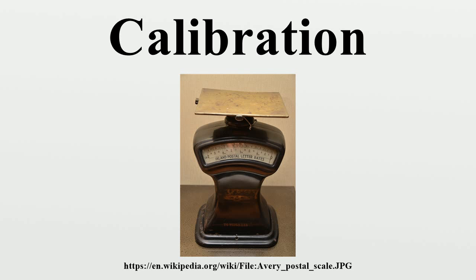This is a simplified example, and it is important that whatever thinking guided this process in an actual calibration be recorded and accessible. Informality contributes to tolerance stacks and other difficult-to-diagnose post-calibration problems. Ideally the calibration value of 100 units would be the best point in the gauge's range to perform a single-point calibration. Multiple point calibrations are also used. A zero unit state — the absence of the phenomenon being measured — may also be a calibration point, or zero may be resettable by the user. There may be specific connection techniques between the standard and the device being calibrated that may influence the calibration, such as in electronic calibrations involving analog phenomena where the impedance of cable connections can directly influence the result.